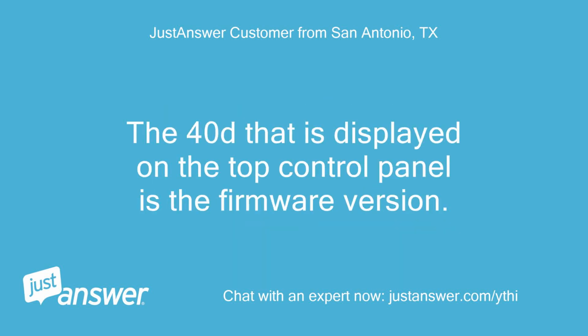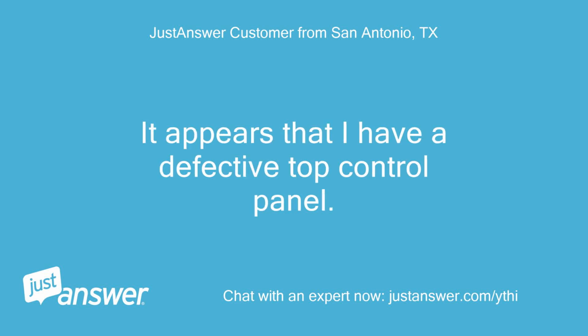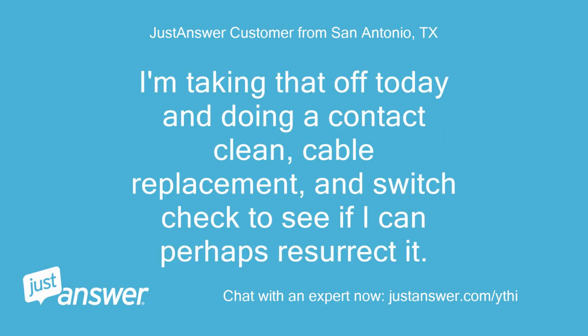The 40D that is displayed on the top control panel is the firmware version. It appears that I have a defective top control panel. I'm taking that off today and doing a contact clean, cable replacement, and switch check to see if I can perhaps resurrect it.